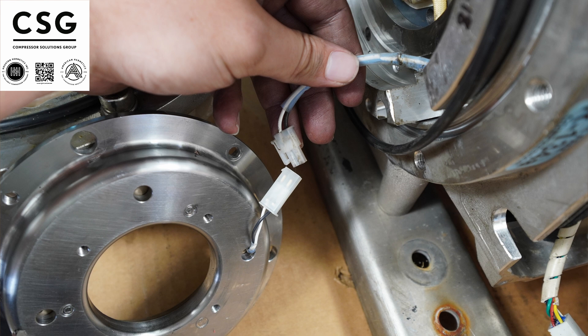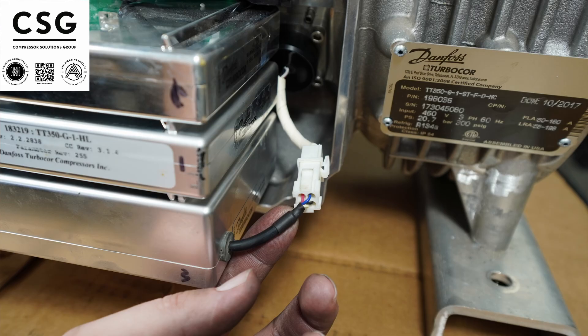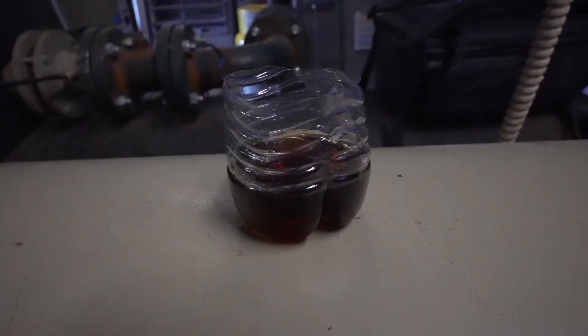There are sensors in there monitoring the shaft position, and as the shaft begins to shift — whether we're spinning up or standing still — the system adjusts the magnetic field to bring the shaft back into the correct orientation. The bearing's current draw constantly fluctuates depending on which part of the coil assembly needs more current to create the necessary field. In summary: mag bearings use a magnetic shaft with a coil assembly to lift the shaft into the air and hold it there, removing the need for oil entirely.